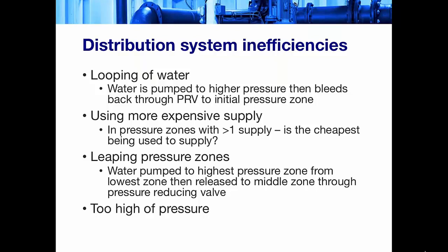Finally, there are some water distribution systems that have too high of pressure. And this often is the result of variable terrain, but too high of pressure leads to more leaks at things like pipe joints, customer service connections. So because there's an energy cost to supplying water, adding pressure zones sometimes can be an energy saver by reducing pressure in the highest pressure zones of your system. With that, hopefully this helps explain the question with inefficient pump stations. But like with so many things with water utilities, your mileage is going to vary. Each system is unique. So understanding the flow of water in your system is probably the first thing to do here. With that, Dawn will continue on with the next question.